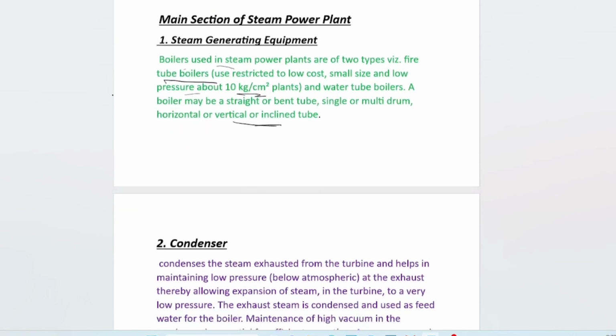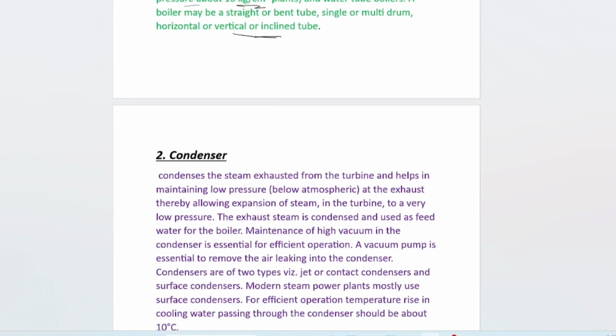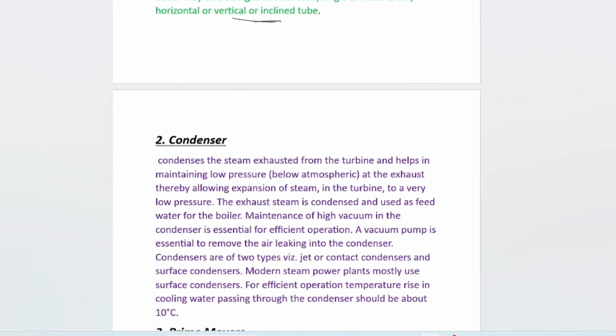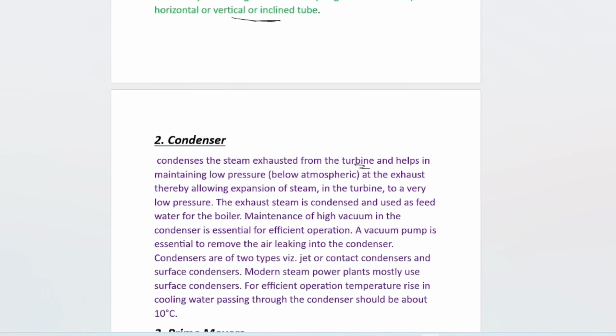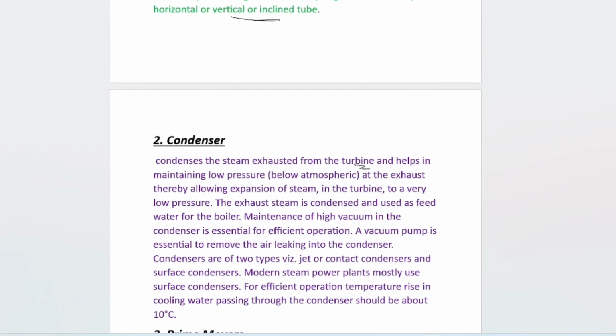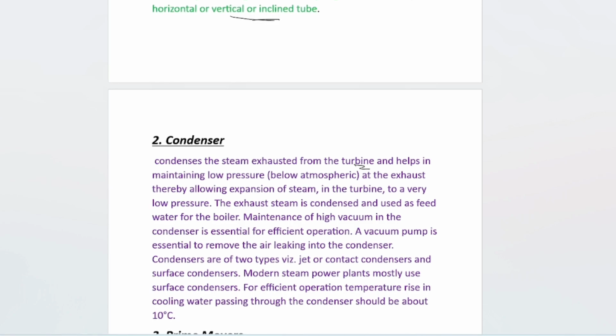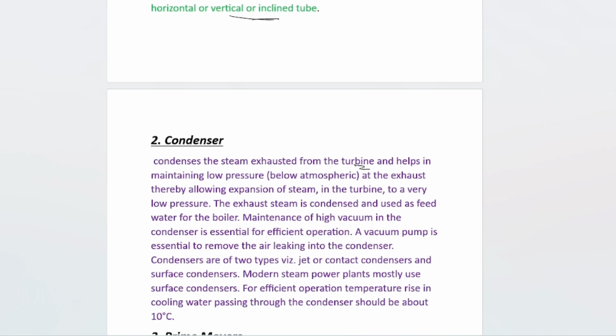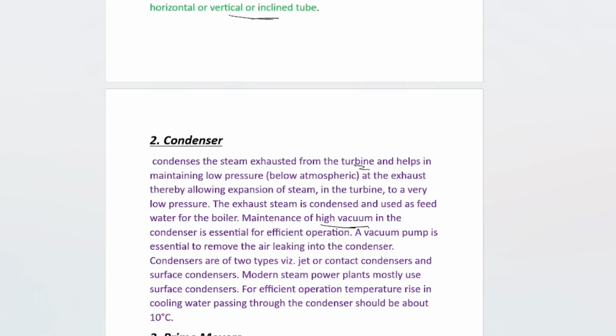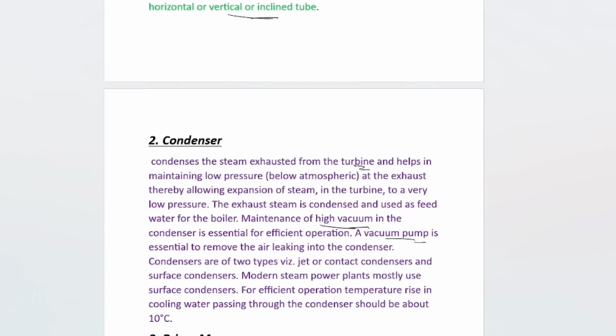Next is the condenser. It condenses the steam exhausted from the turbine and helps in maintaining a low pressure, below atmospheric, at the exhaust, thereby allowing expansion of steam in the turbine to a very low pressure. The exhaust steam is condensed and used as feed water for the boiler. The maintenance of high vacuum in the condenser is essential for efficient operation. A vacuum pump is used to remove the air leakage into the condenser.